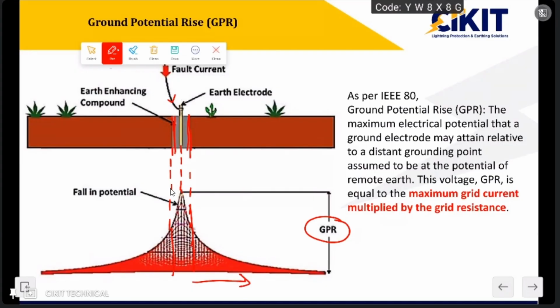At the time of discharge, it won't be at 0 volt. There will be an increase in potential. The level to which the potential increases will be considered ground potential rise. IEEE 80 has mentioned that it is the maximum electrical potential that a ground electrode may attain relative to a remote ground potential. So when I compare the potential of this particular earth electrode with the remote earth electrode, there will be a huge difference in the potential.